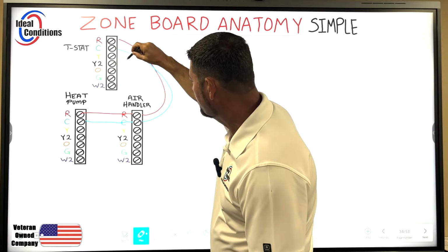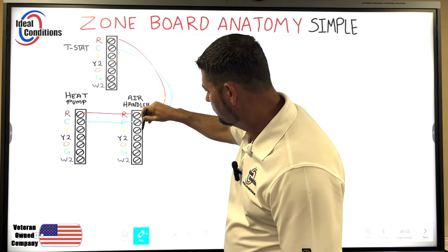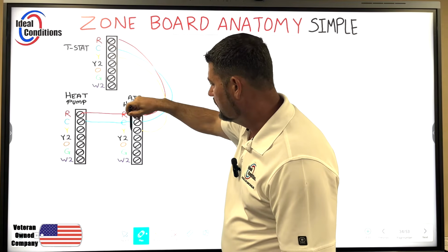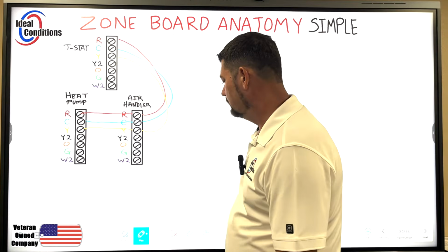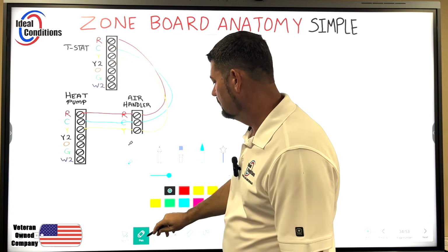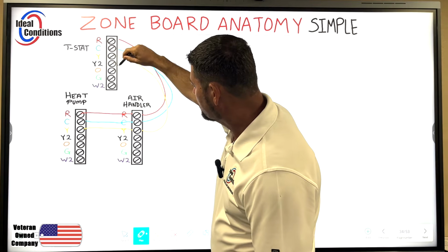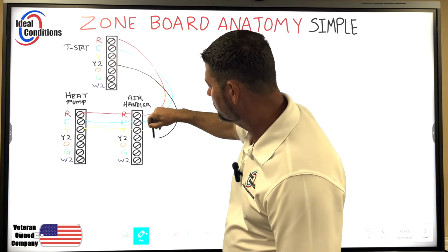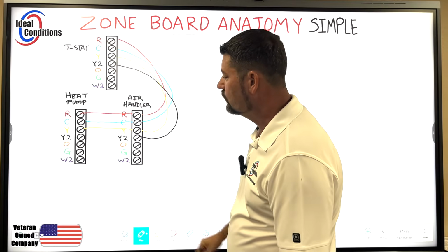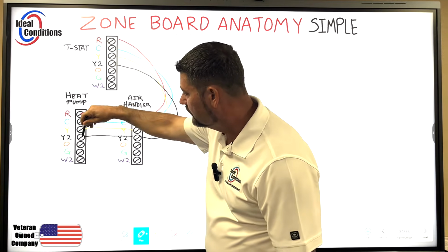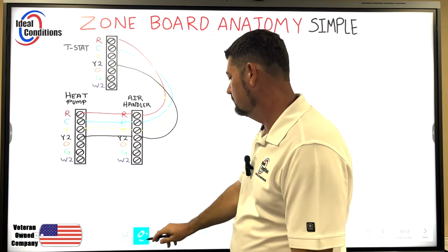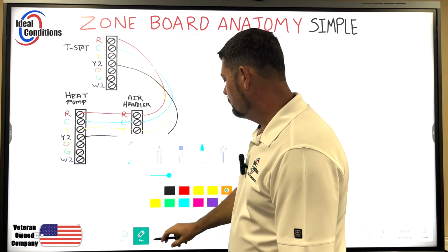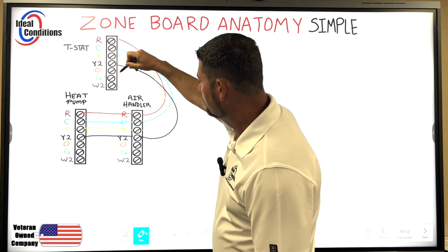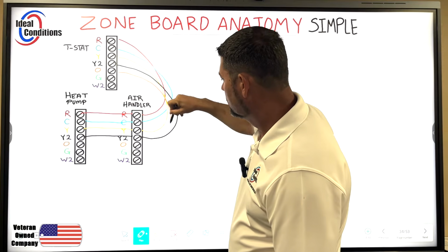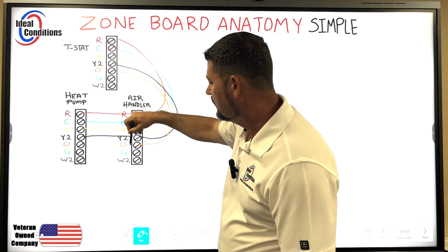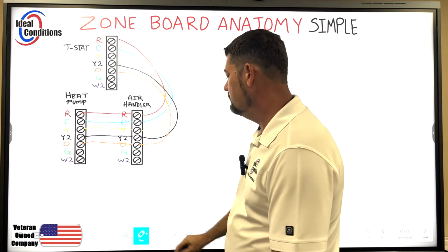So if you can see here, I'm going to come from the thermostat this time. I'm going to come into the air handler, and then out of the air handler we're going to go to the condenser. We're just going to keep doing this. We're going to come out of the thermostat with a Y2. We're going to come into the air handler and tell it, hey, run on Y2. That's going to send the signal outside, hey, run on Y2. Same way if we're energizing the reversing valve. The thermostat will send that signal over to the air handler. Out of that, it'll go over to the heat pump.